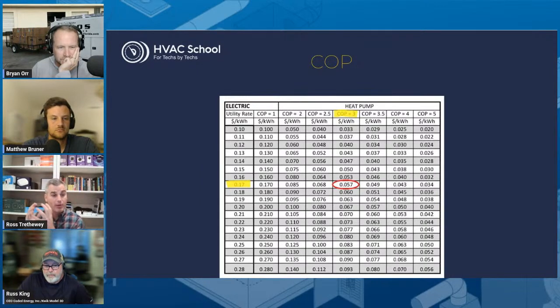And it's based on the heat pump efficiency, but it's also based on the price per kilowatt hour that you pay. So if you're in an area that has a low kilowatt hour price for electricity, and you're putting in a heat pump, it's a no-brainer. It will win against any fossil fuel comparison. But if you're in a place like Massachusetts where we pay 32 cents a kilowatt hour, that's a different animal. Even if you designed and installed the best heat pump on the planet that we know of today, if the operating cost of that heat pump goes up compared to the natural gas furnace that they had in there previously, no matter what, even if you're doing a better comfort, the homeowner is not going to be happy with it.